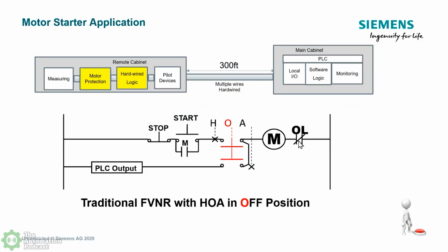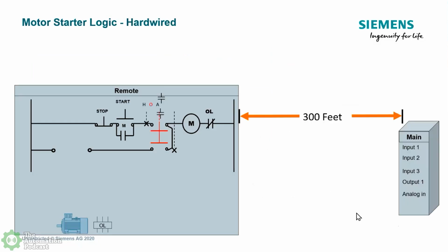And then, of course, you have the overload here that would disrupt if something had happened with the motor in an overload capacity. But notice that the main cabinet still has all the logic, has the software, and it's doing all the monitoring. But then out in the remote cabinet, you might have some pilot devices. You may have a CT measuring something, and then, of course, your overload, and then some hardwired logic like this HOA.